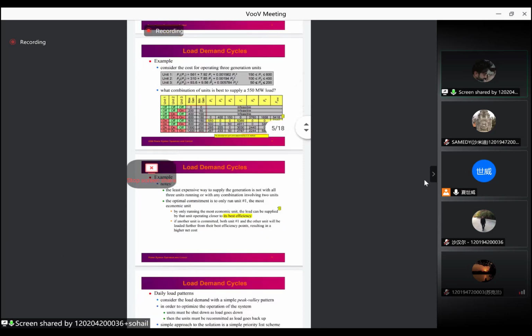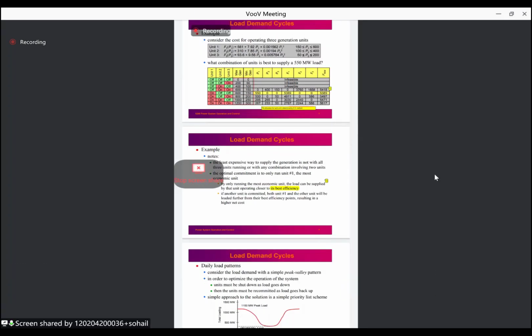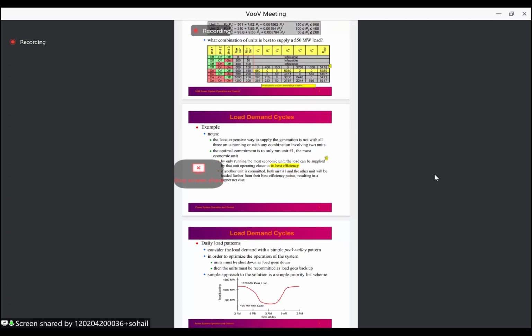Okay, so before going anywhere, I would like to explain unit commitment more. So what is the unit commitment? The optimal selection of combination of units to be committed to meet a particular demand. What is meant by this? For example, we have 3 units in a power plant: unit 1, unit 2, and unit 3. Unit 1 is producing 500 megawatt, unit 2 10 megawatt, and unit 3 is 15 megawatt. What is the demand of the regional load? For example, the regional load requires 25 megawatt. So which units need to be turned on? This is called the unit commitment.